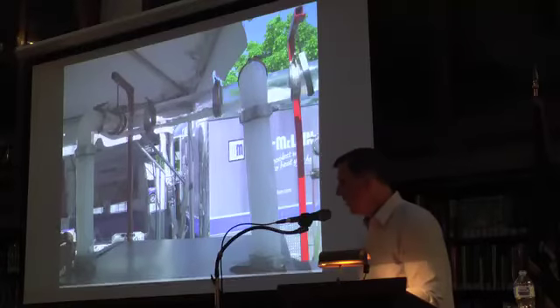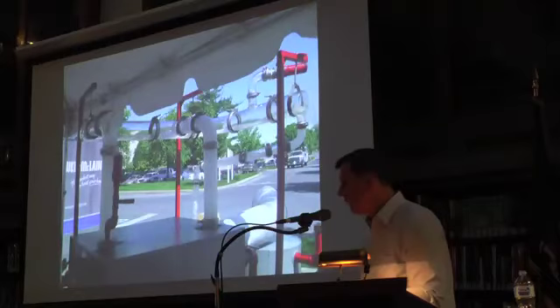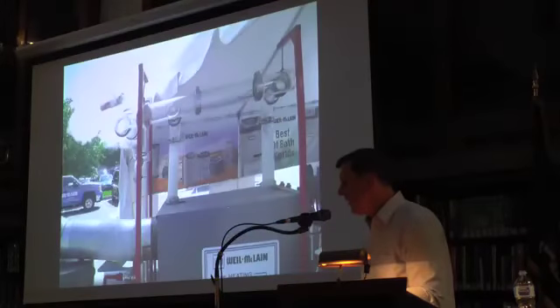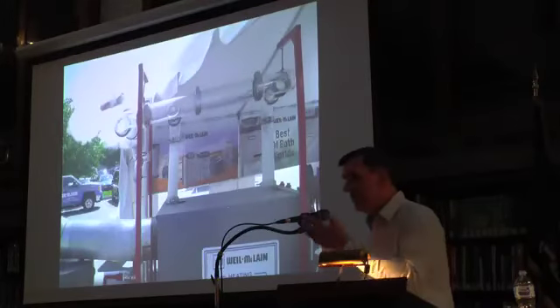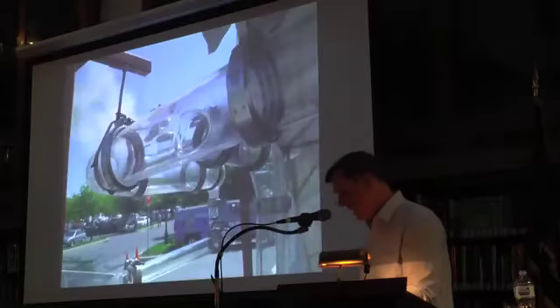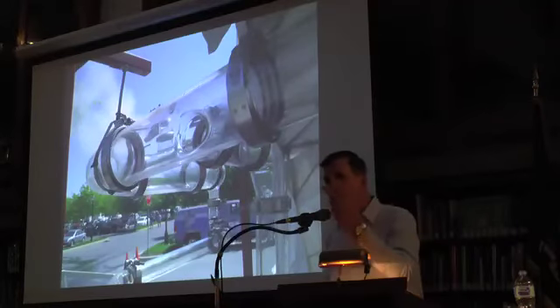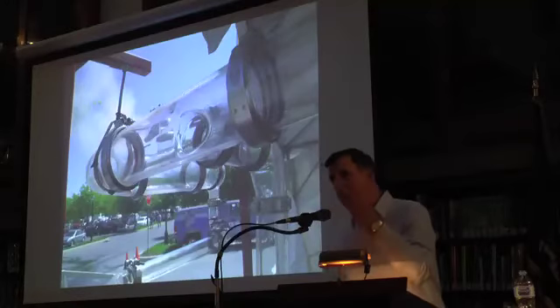So that's cascading over into the header, and it's running for a while. While it's running, what you see coming out is not steam, that's water vapor. We call that steam, but steam you can't see. That's what steam looks like. That's good dry steam. Dry steam means no more than 2% liquid in it. Dry steam looks like air.